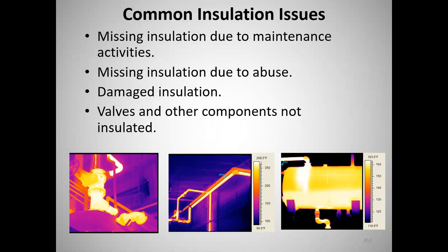I've seen a lot of insulation falling off stuff where they used to have it, or they cut it off to do maintenance. But these guys didn't have a stitch. And that middle, that shows the kind of reddish pipe is cooler. That's the condensate pipe. And the white yellowish pipe is the steam pipe. And they're not very big.